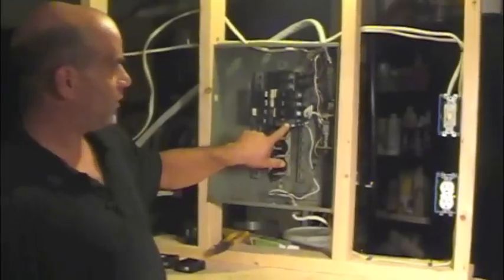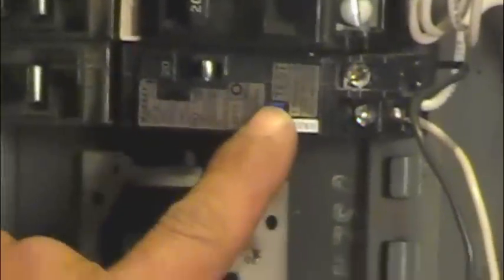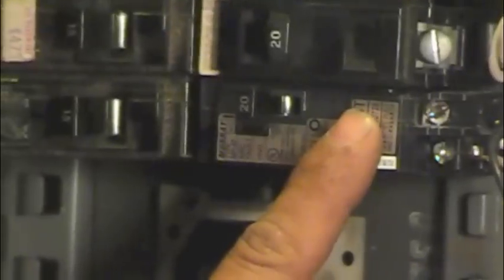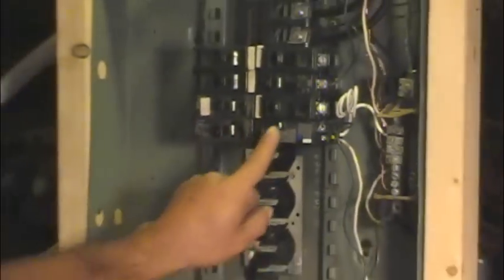On our breaker we have a little blue button. Now when we press this button, you just got to press it in once. Basically what it's saying, if this thing trips, if the breaker trips when I press this button, then this circuit is connected and working good the way it's supposed to be. So let's see what happens.